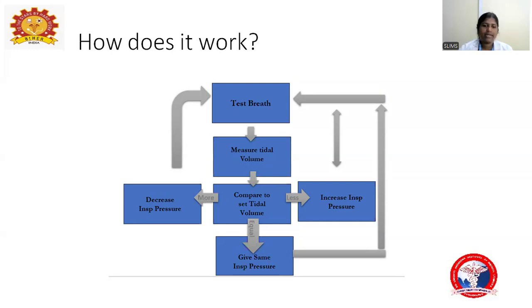So it will compare, and if it is more, it will decrease your inspiratory pressure. If the test breath is less than the set tidal volume, it will increase your inspiratory pressure and will deliver the volume. And if the test breath is the same as the set tidal volume, it will deliver the same inspiratory pressure. And the cycle continues for each breath.